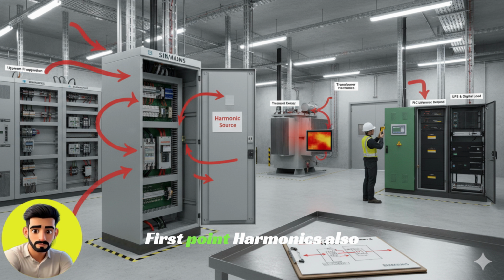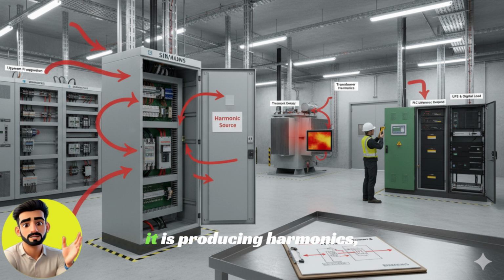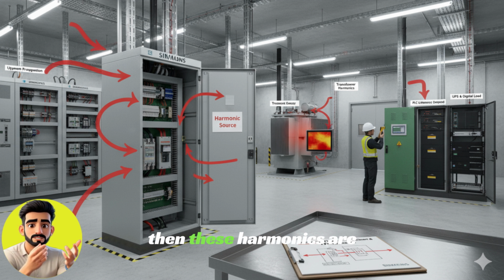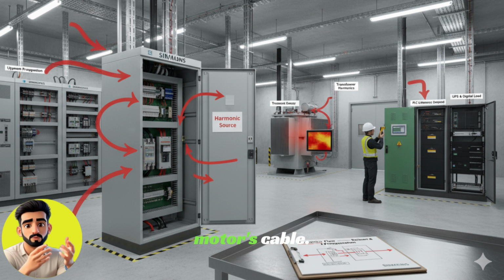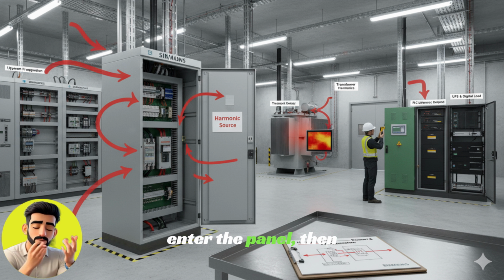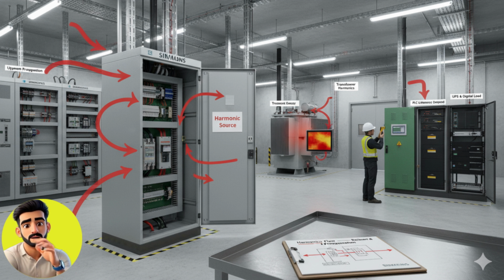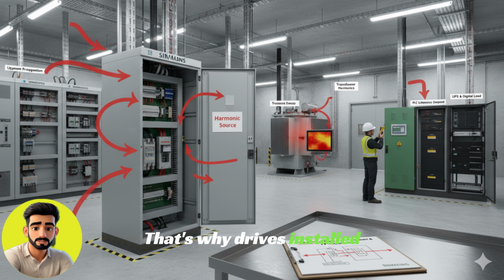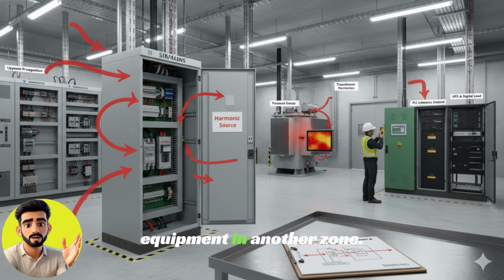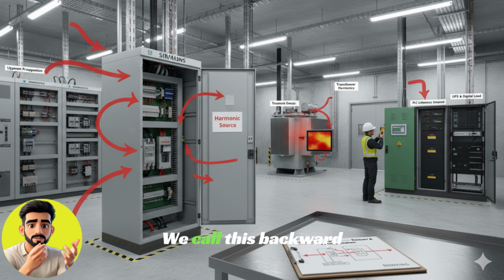First point. Harmonics also travel upstream. If a motor has a VSD installed and it is producing harmonics, then these harmonics are not only in the motor's cable. They exit the cable, enter the panel, then go to the MCC and reach the transformer. That's why drives installed in one corner of the plant can disturb equipment in another zone. We call this backward propagation.